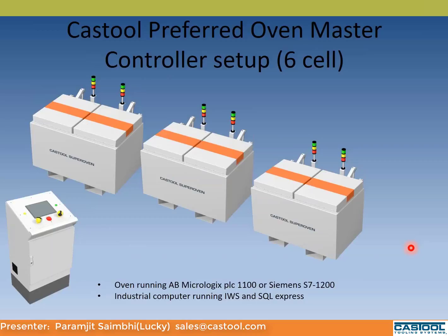So the Castool preferred oven master controller setup, this is showing you a 6-cell setup. So what we're saying is, let's say we're going with our standard, most economical approach. You would put PLCs like a MicroLogix 1100 or an S7-1200, a Siemens one, in each cell, and then you'll have a centralized screen. So there's no PLC inside, and you have one screen communicating to all the ovens. Obviously this would be an industrial computer running SQL Express database, so you can save all the events and transactions to a centralized database, and you can run reports and stuff. It's the most cost-effective approach.